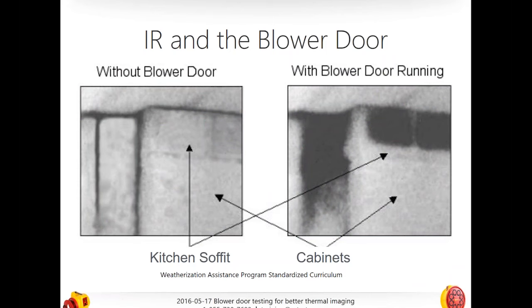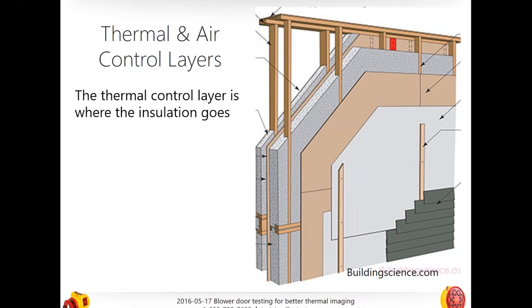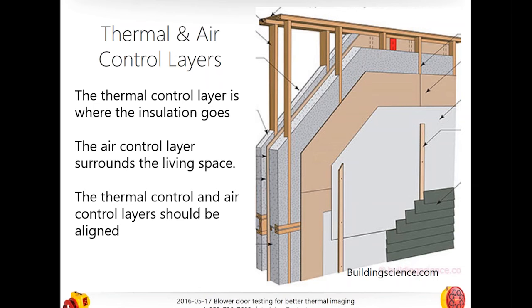Here is a simple black-and-white image from the Weatherization Assistance Program standardized curricula built by NREL and the Department of Energy. Here is a picture of a kitchen soffit — very difficult to see before the blower door. Then we run the blower door, and even without high resolution, we can see there is a gigantic difference.